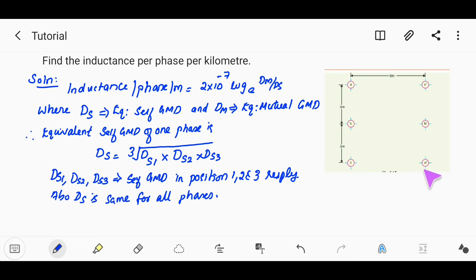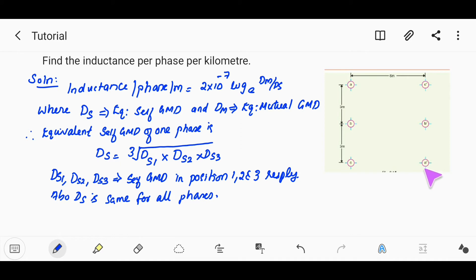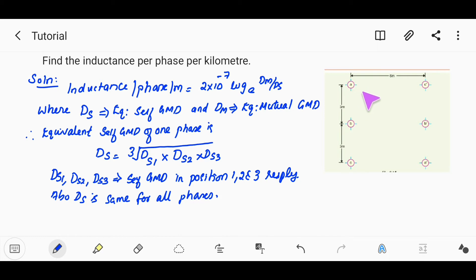The geometry forms an equilateral triangle, and the distance between conductors uses the hypotenuse of this triangle. Using the mutual GMD formula, we can find the mutual GMD with respect to each conductor pair.